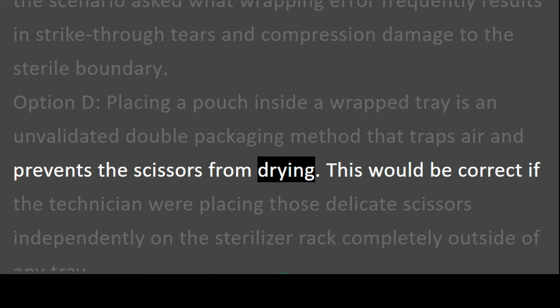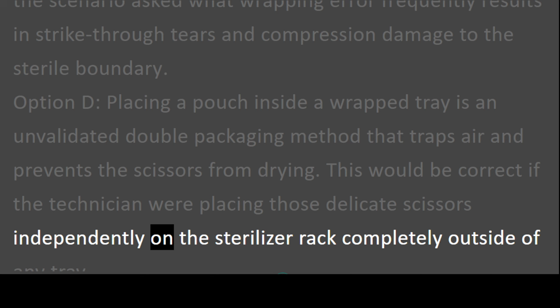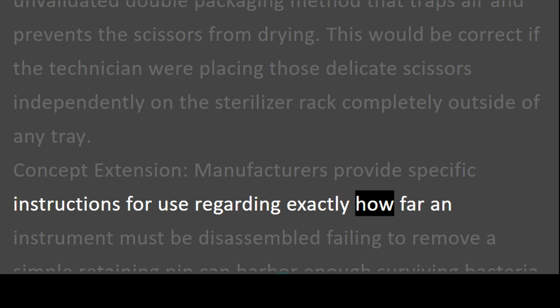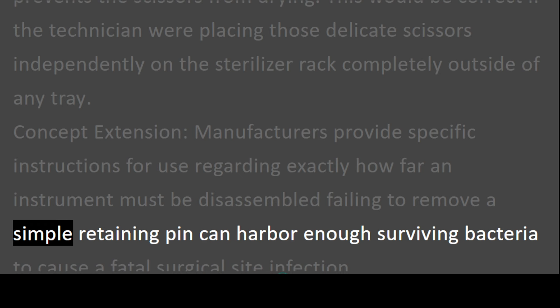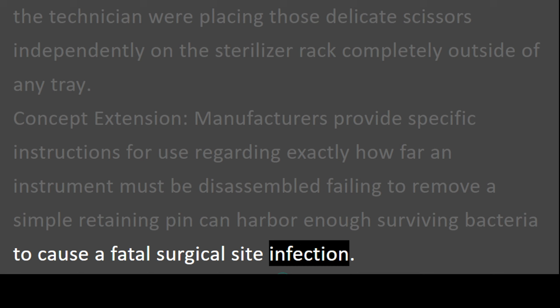Option D. Placing a pouch inside a wrapped tray is an unvalidated double packaging method that traps air and prevents the scissors from drying. This would be correct if the technician were placing those delicate scissors independently on the sterilizer rack completely outside of any tray. Concept extension. Manufacturers provide specific instructions for use regarding exactly how far an instrument must be disassembled. Failing to remove a simple retaining pin can harbor enough surviving bacteria to cause a fatal surgical site infection.